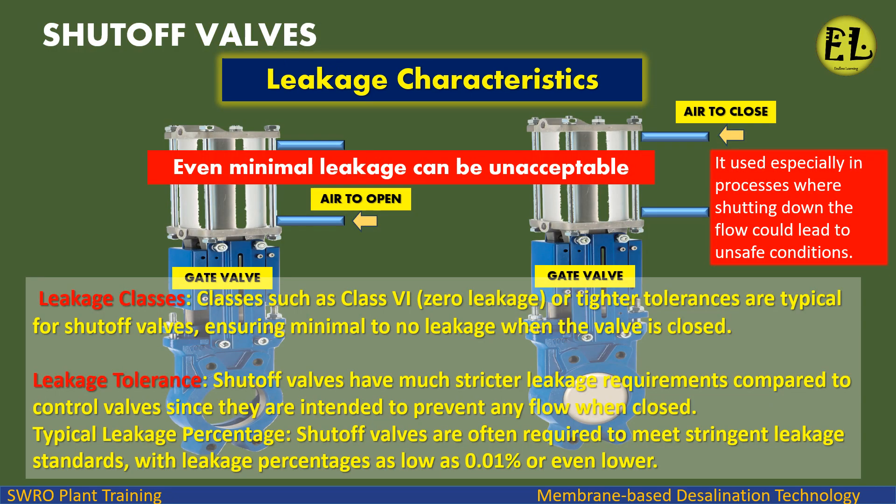For shutoff valves, leakage classes such as Class 6 or zero-leakage tolerances are typical, ensuring minimal to no leakage when the valve is closed. Shutoff valves have much stricter leakage requirements compared to control valves, since they are intended to prevent any flow when closed. They are often required to meet stringent leakage standards, with leakage percentages as low as 0.01% or even lower.